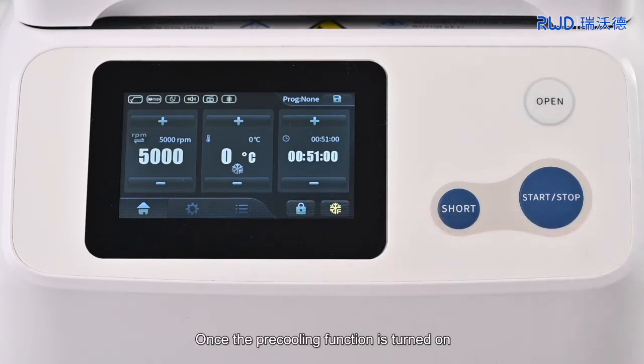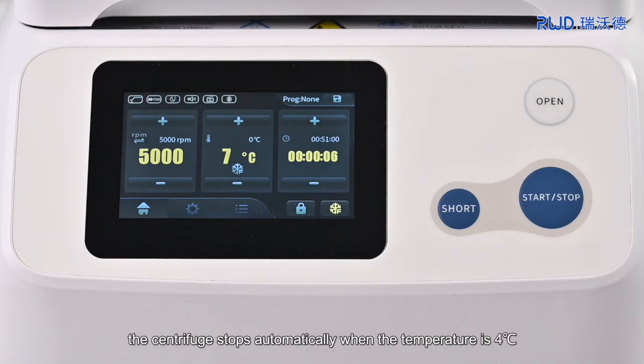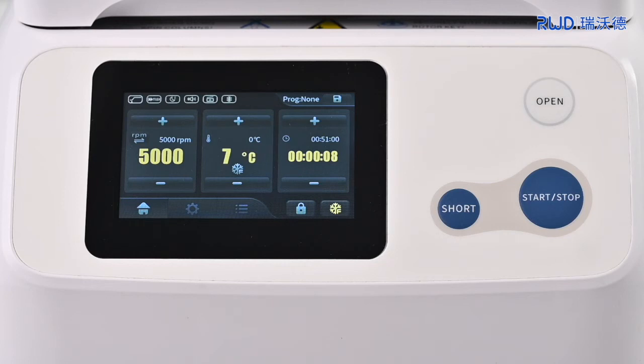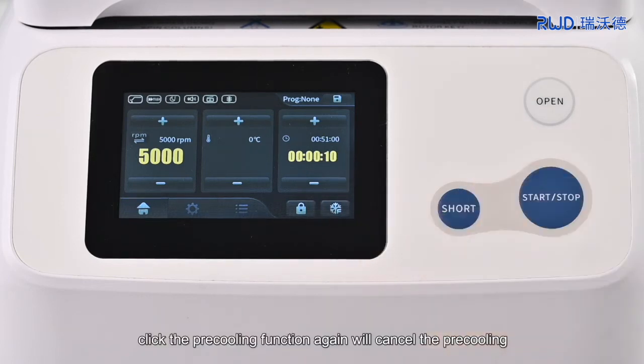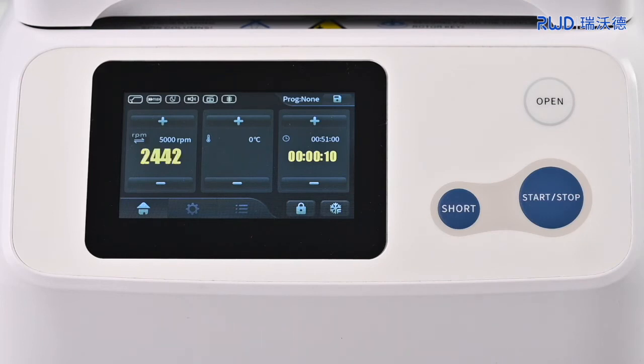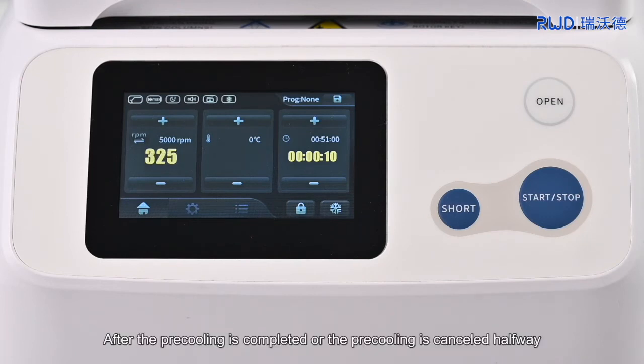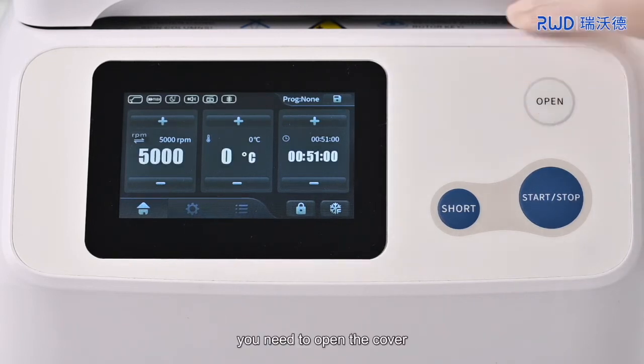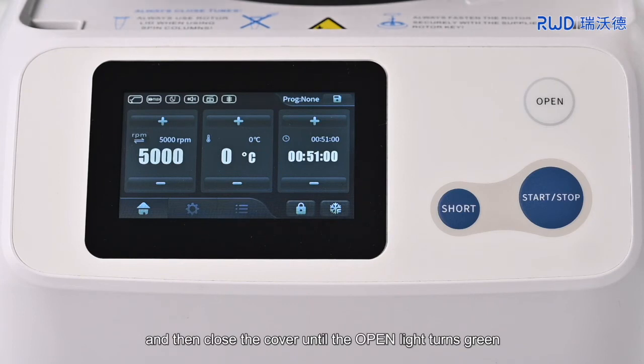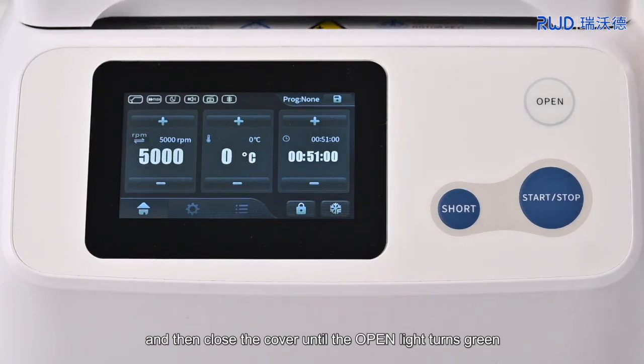Pre-cooling mode. Once the pre-cooling function is turned on, the centrifuge will work at 500 RPM. The centrifuge stops automatically when the temperature is 4 degrees Celsius. During the pre-cooling process, click the pre-cooling function again to cancel the pre-cooling. After the pre-cooling is completed or the pre-cooling is canceled halfway, you need to open the cover and then close the cover until the open light turns green.